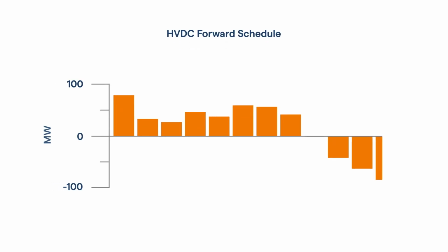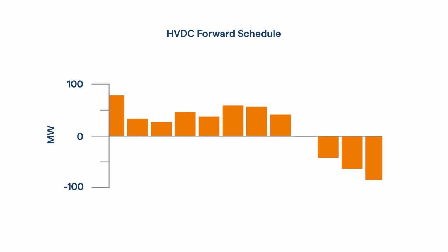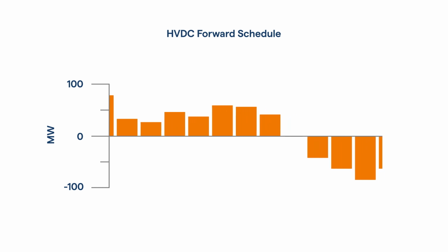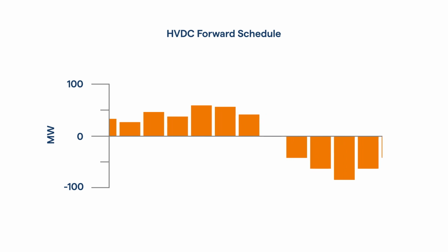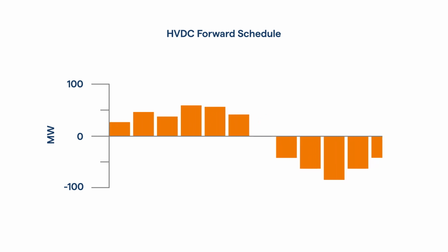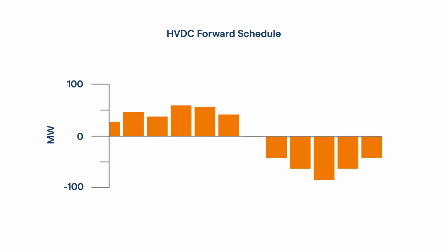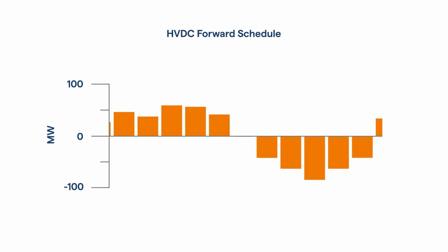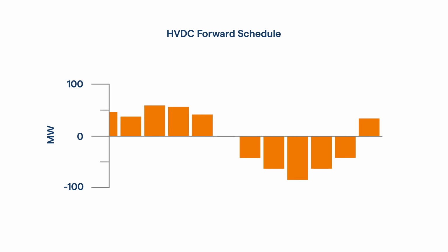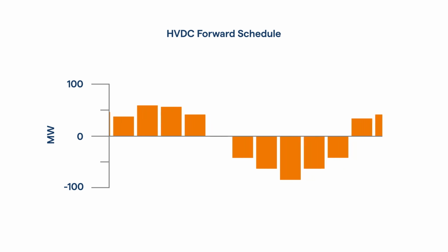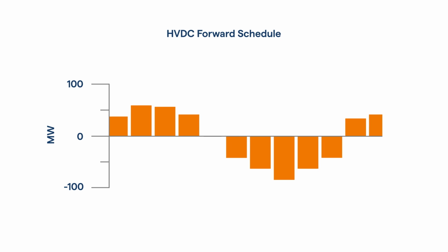In the forward schedules, in order to normalise the pricing between the two islands, pole minimums are not modelled. In the RTD schedules, as assets cannot be dispatched outside their declared capability, the pole minimums are modelled. In a monopole scenario, the system coordinator checks the forward schedules for the HVDC transfer forecast, which is compared against actual inputs, as they will vary.